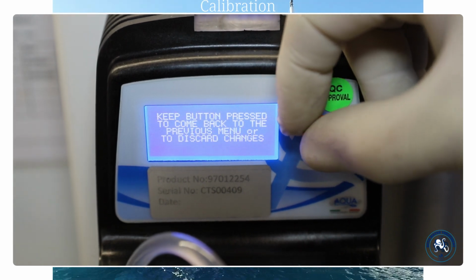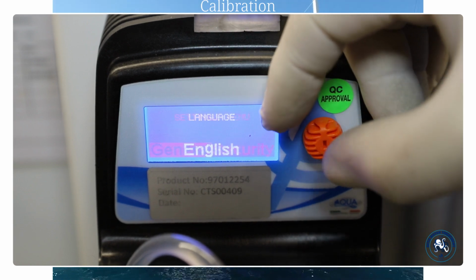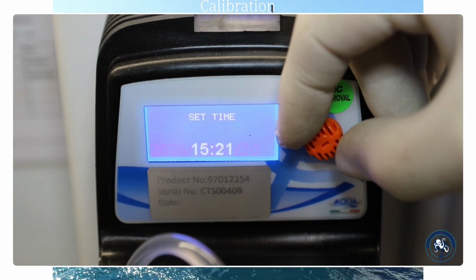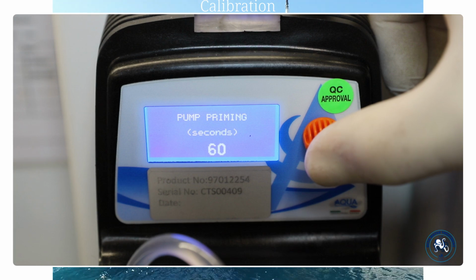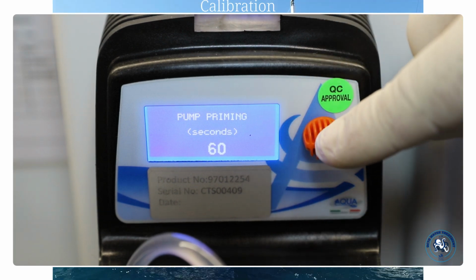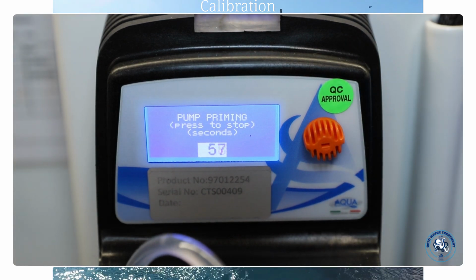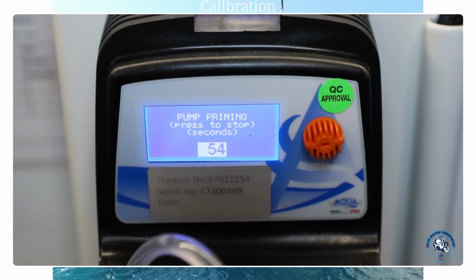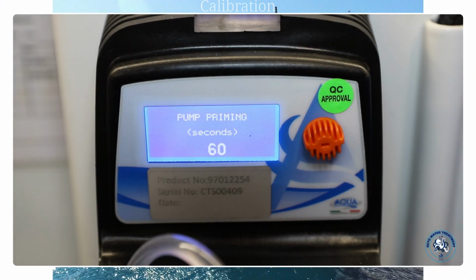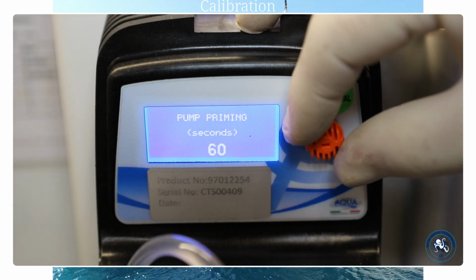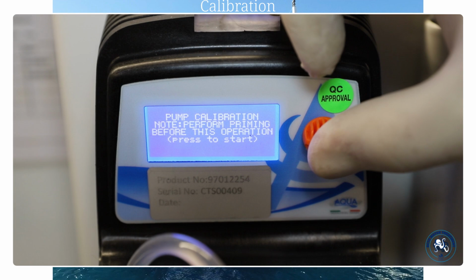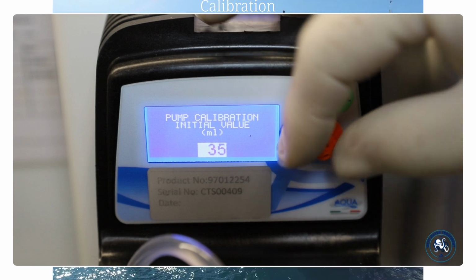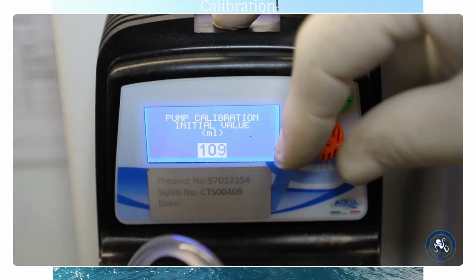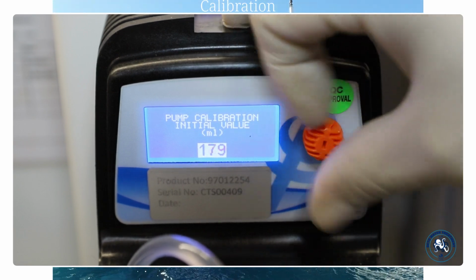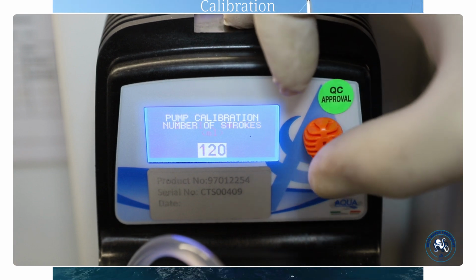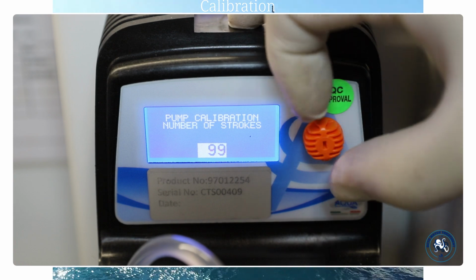Then go back into the settings a second time to access the priming section. Once you are in the priming section, click to prime the pump. Do this until all the air bubbles have discharged by the injector, and restart this stage as many times as necessary before carrying out the calibration. Once this stage is finished, proceed to calibrate the pump by pressing the button once. For this example, we are setting it at 200 milliliters. Then press Enter. Select 100 strokes.